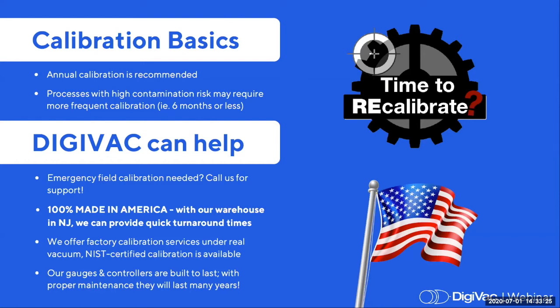Here we'll discuss some basics of our calibration process. We recommend calibration annually for customers in medium to clean environments. Processes with higher contamination risk might require more frequent calibration, about 6 months or less. We recommend shorter intervals for customers who do heat treating, metallizing, gold plating, sintered metals, oil distillation and processing. Short path customers are very prone to contaminated sensors. So in that case, we recommend calibration more frequently than not.